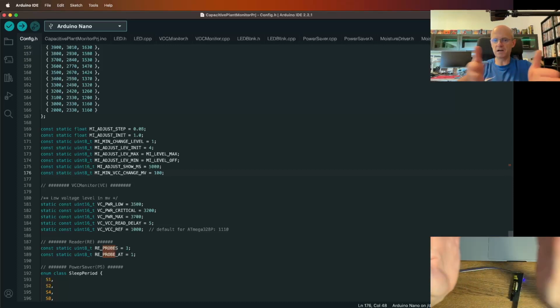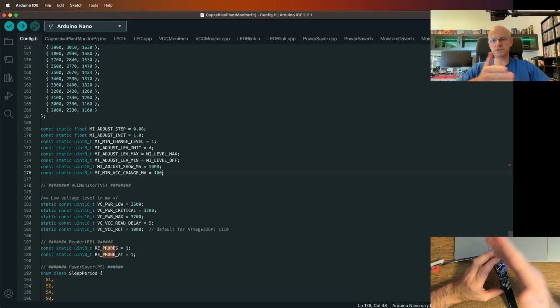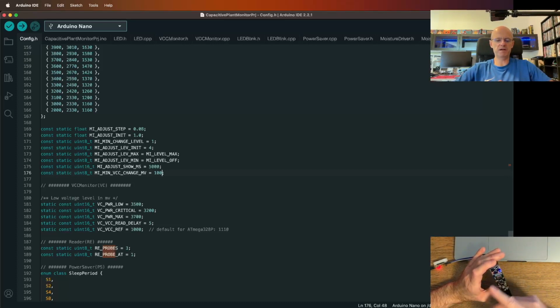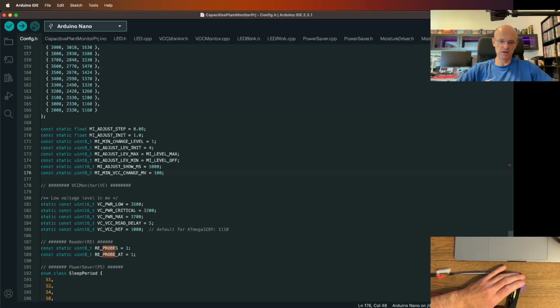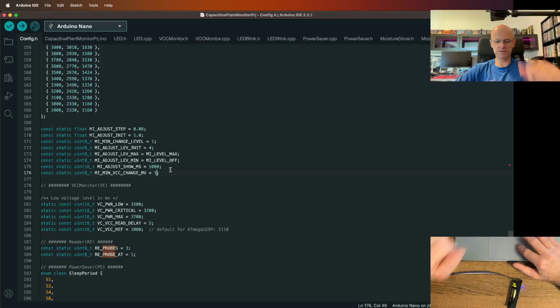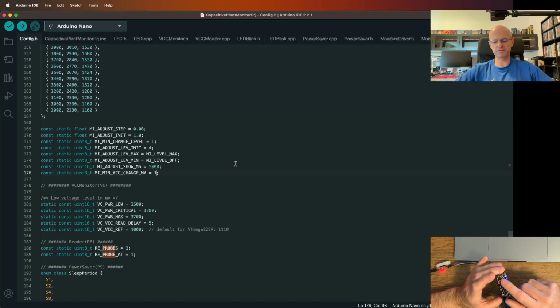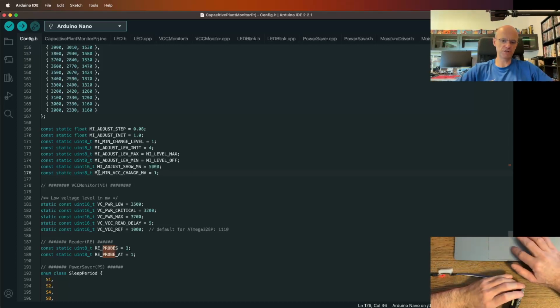Why do we want to pick up only larger voltage changes? Because every measurement has a slight difference — it's not perfect. If your moisture level is right on the corner between, say, level 3 and 4, and you pick up every smallest voltage change, it can cause flickering, jumping between level 3 and 4. So you don't need such precision when reading voltage normally — 100 millivolts is okay, but for calibration you want as good precision as possible, so we're changing it to 1 temporarily. Later on, if you observe the LEDs flickering between one level and another, you'll know you have to change this variable to avoid it.